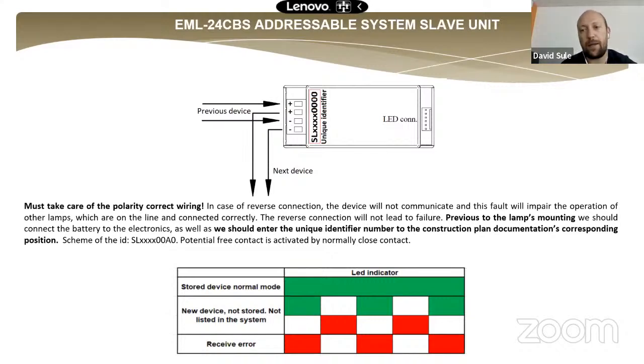If we install a new light into the system, that will show the fast green LED, green, red, blinking. So it's a new device. The address is not stored by the panel, so we have to search for this new light.